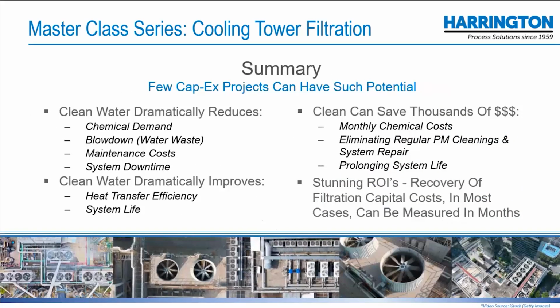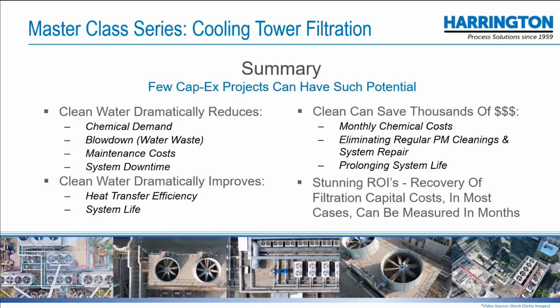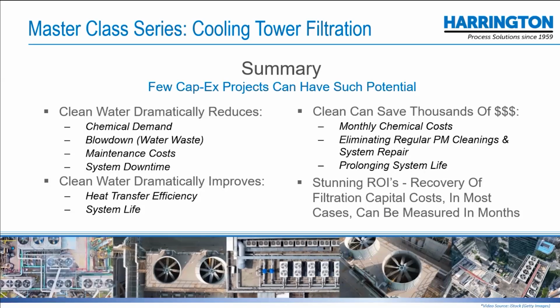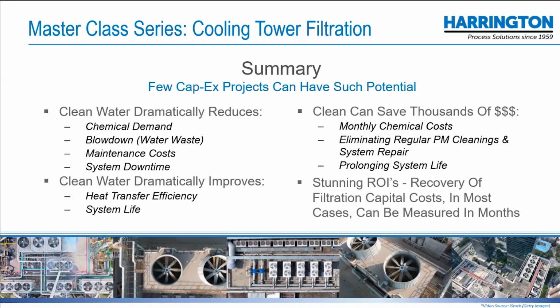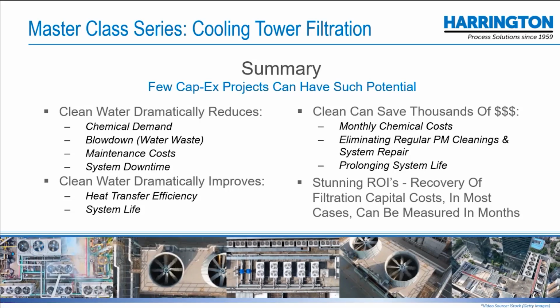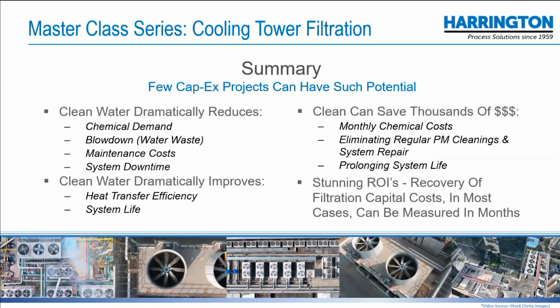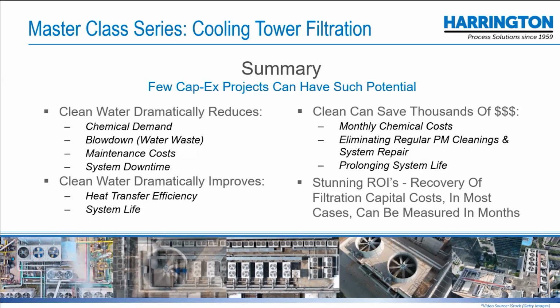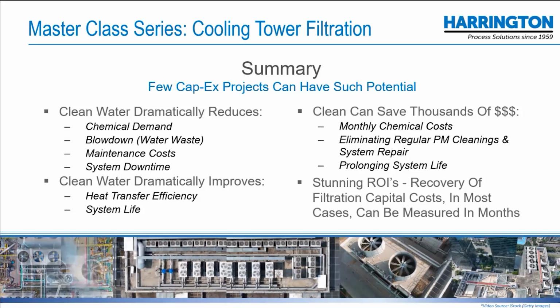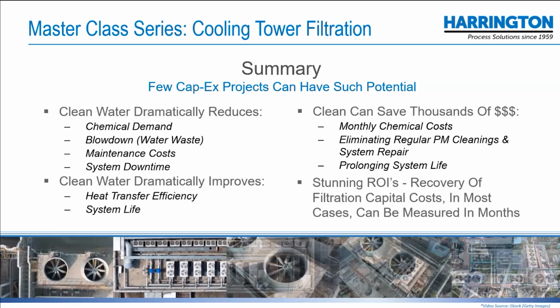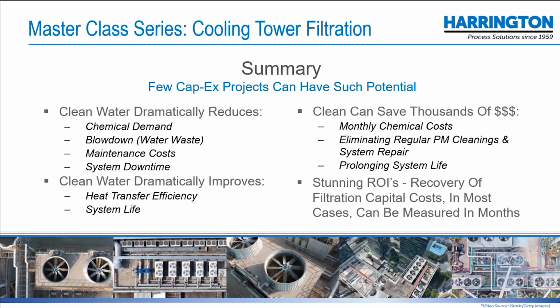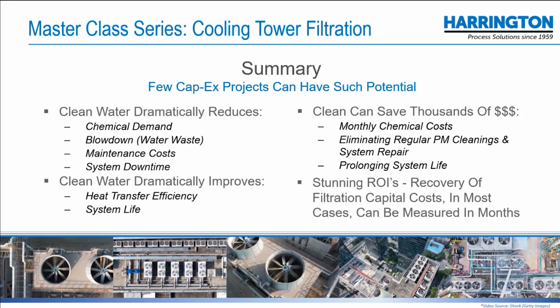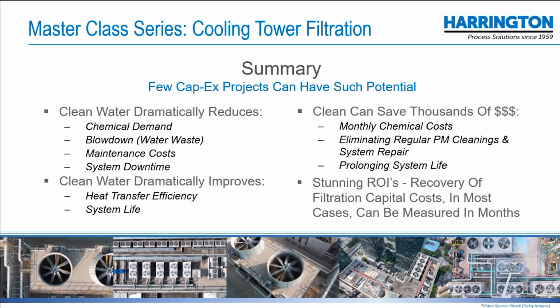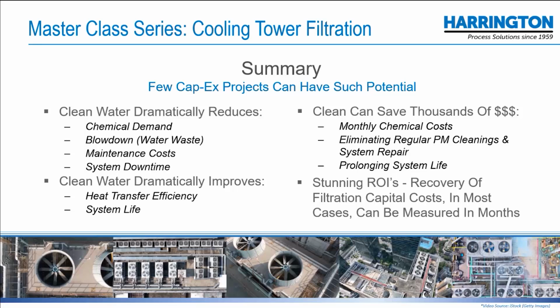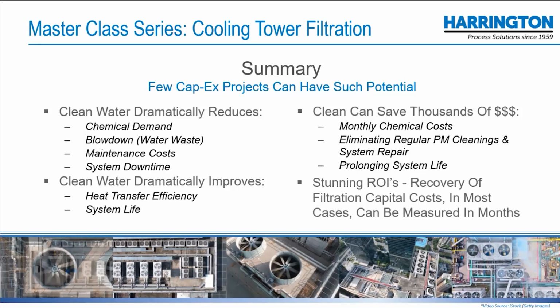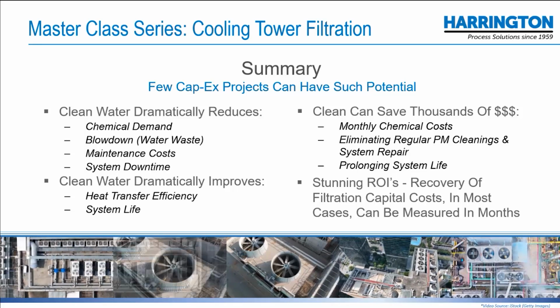To summarize, clean water dramatically reduces chemical demand, blow down (the wastewater that's drained off of the reservoir), maintenance costs, and system downtime. It also improves the system efficiency and life and can save thousands, tens of thousands of dollars at times in monthly chemical costs and regular PM and cleaning, system repair. It'll make your system last longer. It has a stunning return on investment because the filters, even when skidded with pumps, are just not that expensive. And in most cases, you can anticipate an ROI of a year or less.